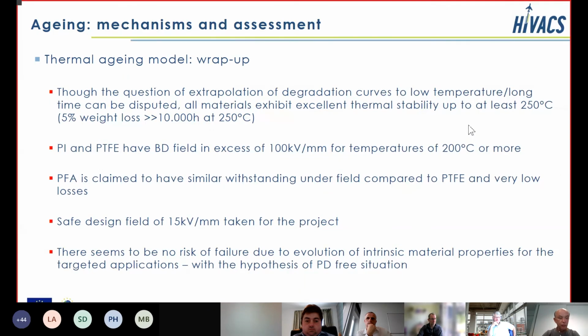So, if I wrap up the work on the thermal modeling, of course we can question the validity of extrapolating degradation curves achieved in a relatively short time to low temperature. We can have different processes at lower temperature. For example, maybe oxygen diffusion can be something important. That is a first approach. The second point is that we have a high breakdown field for PI and PTFE at temperatures of 200 degrees C and more. PFA is claimed to have similar withstanding under field compared to PTFE, according to the providers. We use a relatively safe design field of 15 kilovolt per millimeter for designing the cable, so we are far from these limits. And we believe there is no real risk of failure due to intrinsic material evolution, supposing that we have no PD in the materials. So that was for the theoretical aspects.